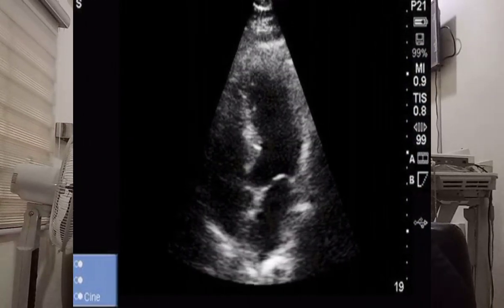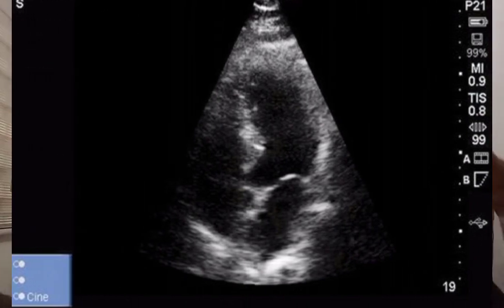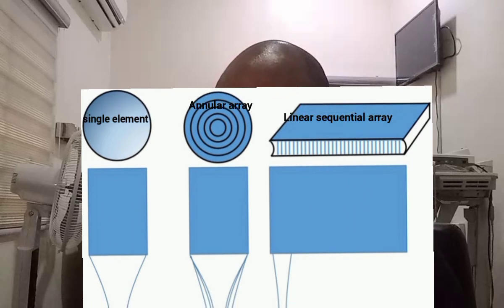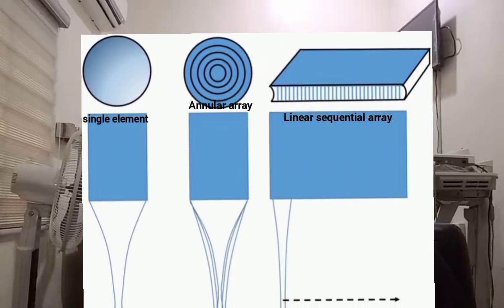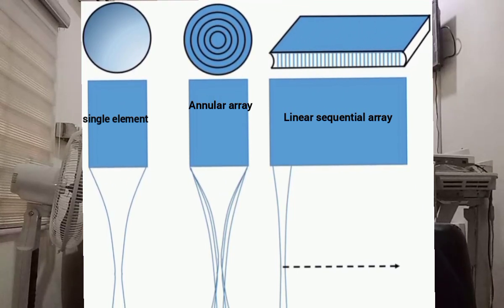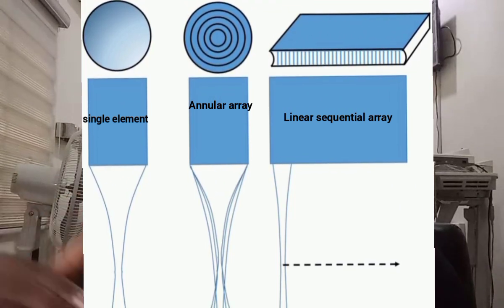It produces a sector field of view or a pie-shaped display in which the near field is narrower and the far field becomes progressively wider. The mechanical sector transducers were of two types: the single element transducers, which are always with fixed focus, and the annular array transducers, which have a variable focus.